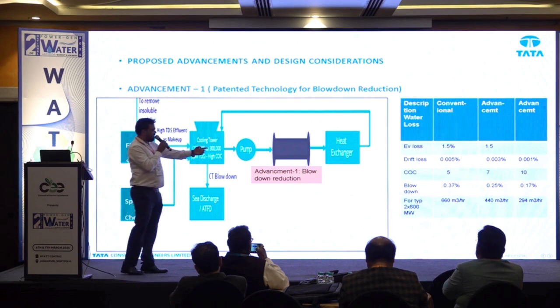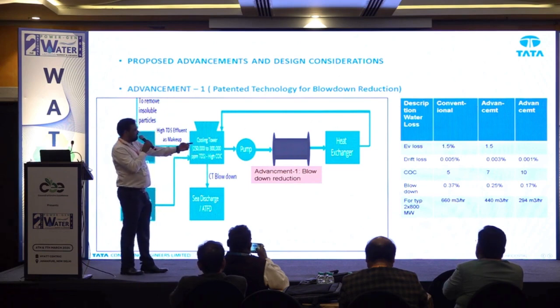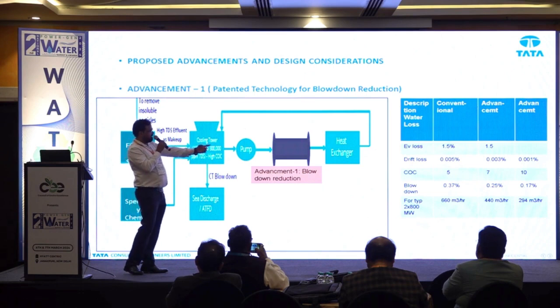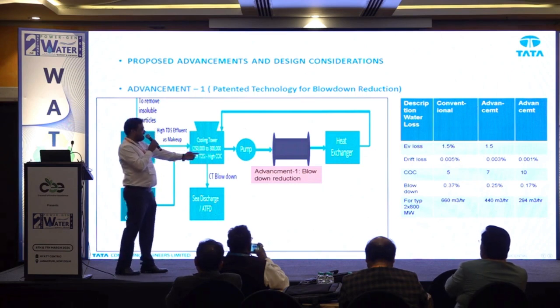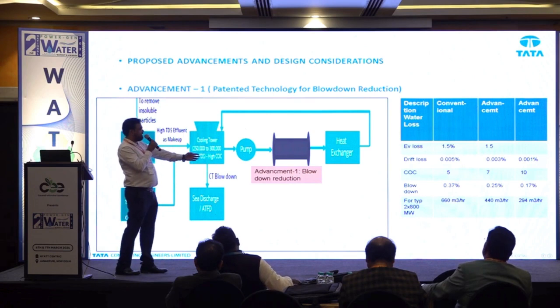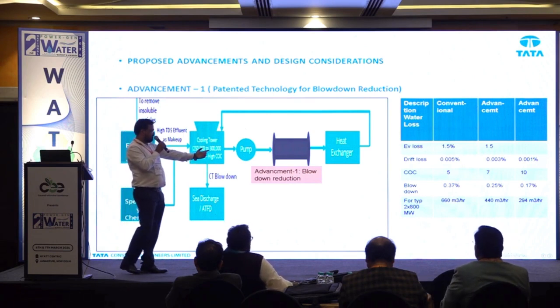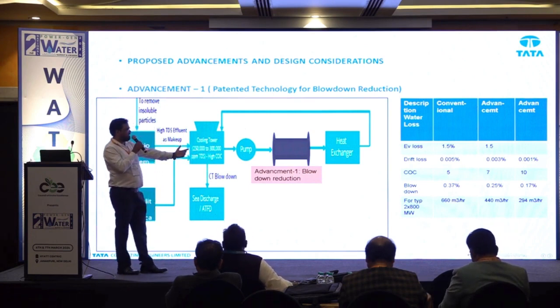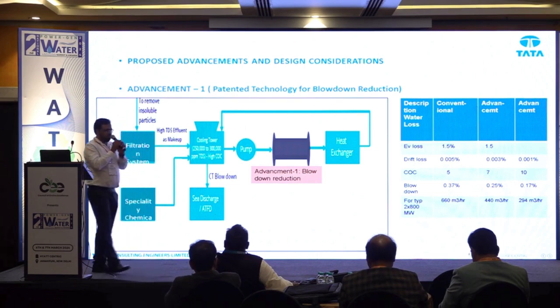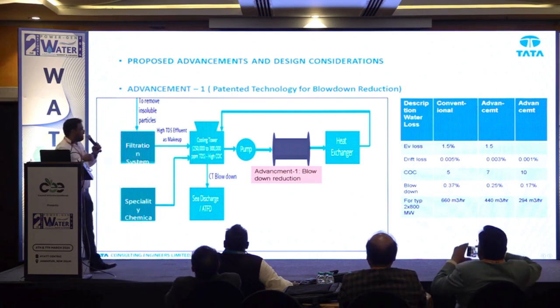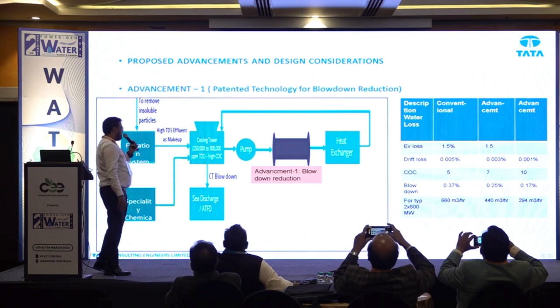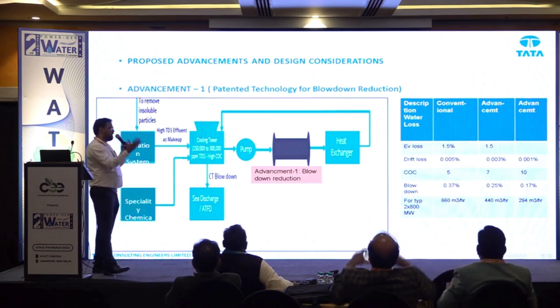So this is actually the advancement which I discussed, the blow down reduction method. We can see with COC 5, what is the quantity of blow down? 0.37%, and with 7, 0.25%. So for a typical 2 into 800 megawatt, 660 meter cube per hour, which we are doing, it will become 440. So that is available.